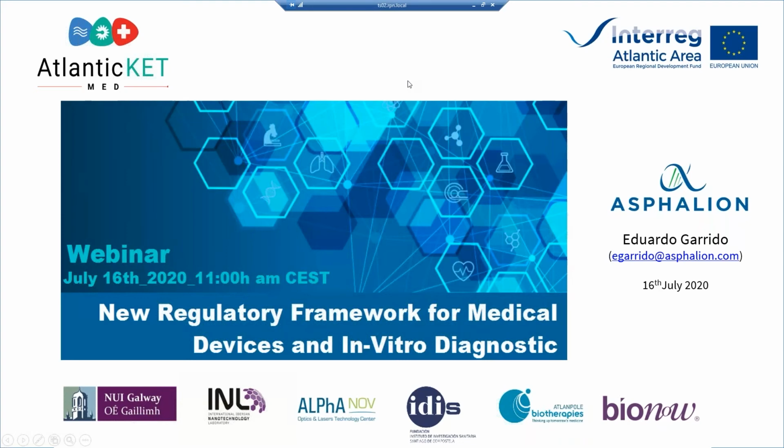I mean, for instance, if you've got a software that is just assisting in the imaging of certain sections of skin, let's say, it can be classified as a class 1. But if this software is aiming at the diagnosis, it's telling the doctor which should be the diagnosis, it's going to go to class 2A. And it obviously depends on the illnesses you want to treat. So it really depends on the indications you want to give to your device.